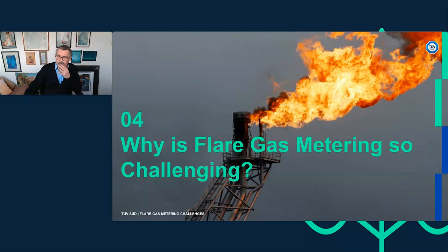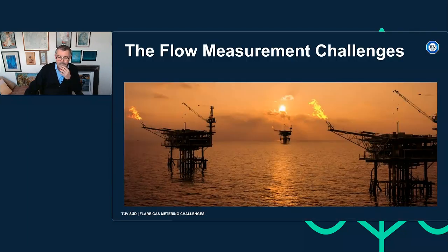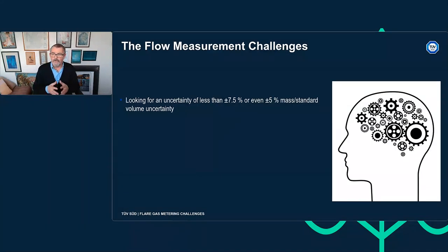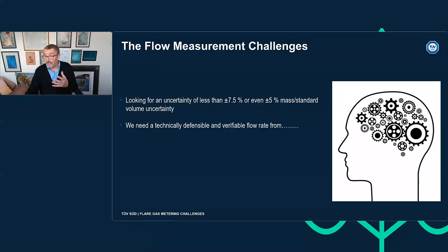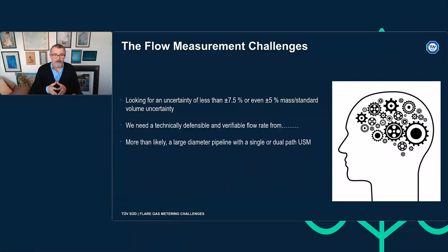Okay, the next challenge for me as to why flare gas metering is so challenging, well, that's the actual flow measurement itself. As I mentioned, most flares have a meter. It's usually an ultrasonic meter, sometimes a thermal mass meter. And generally speaking, regulators and operators are looking for an uncertainty, an accuracy, if you like, if you're not a metrologist, of 7.5%, or even less than that, sometimes 5%, on the mass flow rate or the standard volume flow rate. More and more often now, we need a technically defensible flow rate, something that can be verified independently. And for most operators, they're likely to be using a large diameter pipeline with a single or dual path ultrasonic meter.